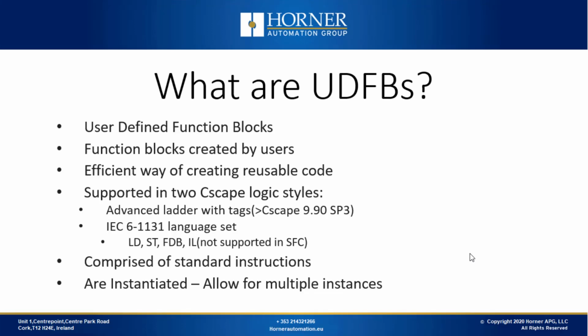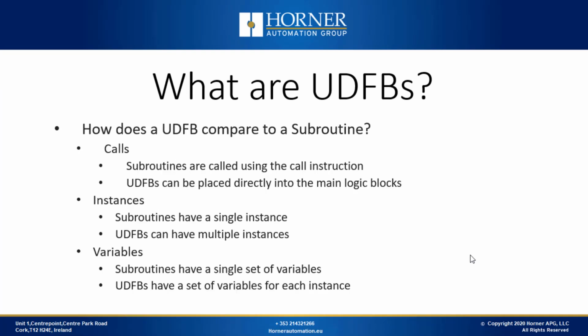Let's start by answering the question, what are user-defined function blocks? As the name implies, these are function blocks that are created by users. It is a very efficient way of creating reusable code and is supported in both IEC 61131 logic and tag-based advanced ladder logic. UDFBs are comprised of standard instructions, and one of their key features is that they are instantiated, meaning they allow for multiple instances of themselves that can be scattered across your code to be ran all at once.